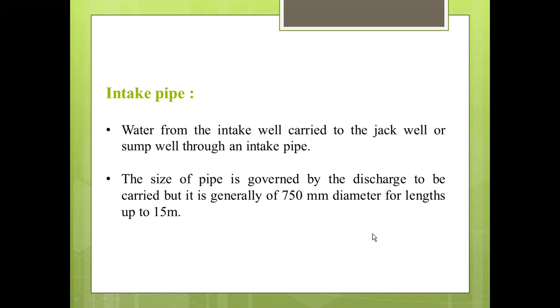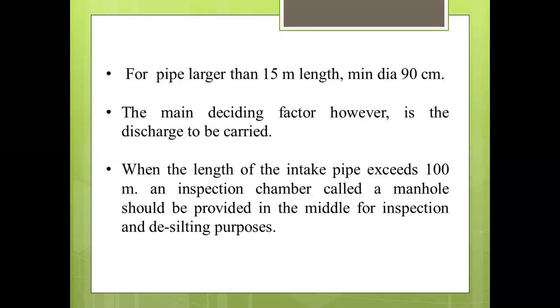Water from the intake well is carried to the jack well or sump well through an intake pipe. The size of the intake pipe is governed by the discharge to be carried, but it is generally 750 mm diameter for lengths up to 15 m. For pipes larger than 15 m in length, the minimum diameter should be 90 cm. The main deciding factor, however, is the discharge to be carried.